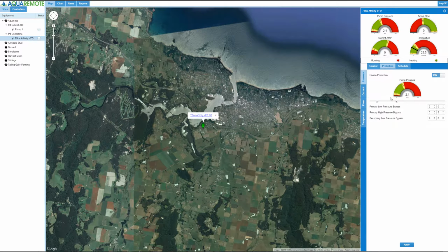Each system has a protection set for pressure, current, flow and temperature. Each one of these is set by moving the slider and applying enable. There are bypass timers for each one of the features, as you may wish to line fill or change the duration before a shutdown.